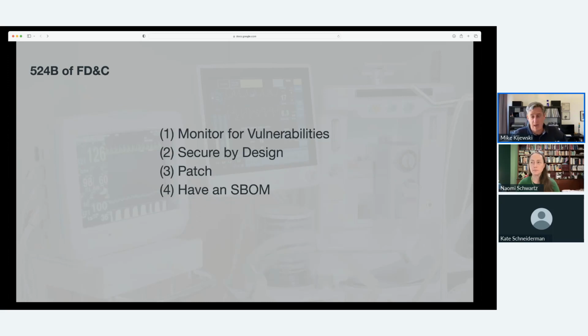Number three, there needs to be a plan to patch, right? It's not acceptable to release a medical device that runs software and has cybersecurity considerations for which you can't patch that device, unless there are some very, very special circumstances in place. And then finally, device submissions should include an SBOM. I think the language in the Omnibus bill says cybersecurity bill of materials, a CBOM, as the 2018 guidance does. I believe we've updated that to SBOM, and everything I have heard is that the final draft of the pre-market guidance will have SBOM, not CBOM. Naomi, does this seem like a good summarization of what the FDA is asking for as part of the submission? That's exactly right.